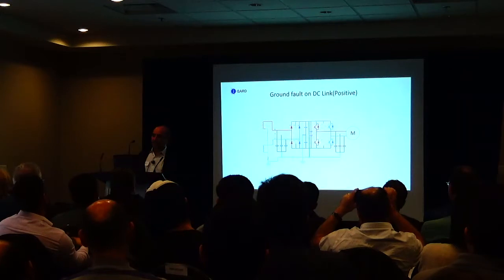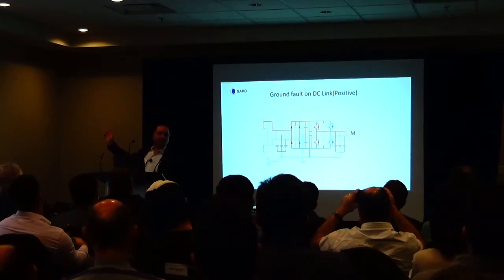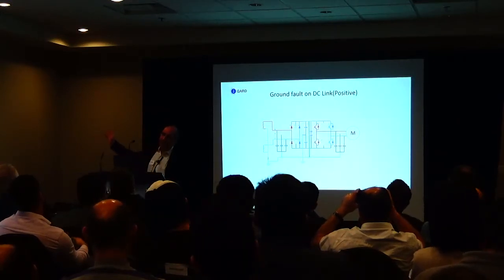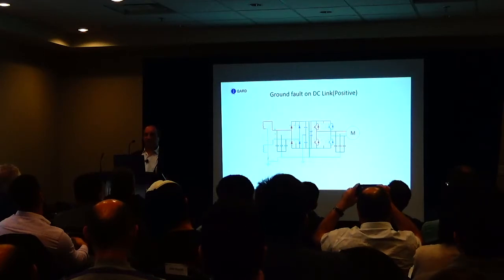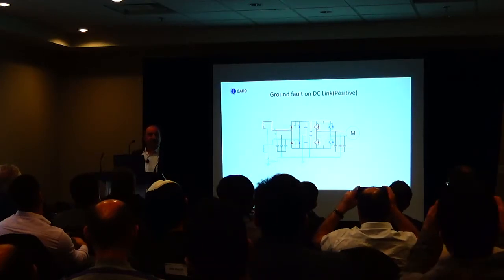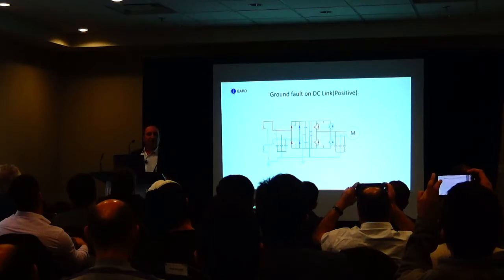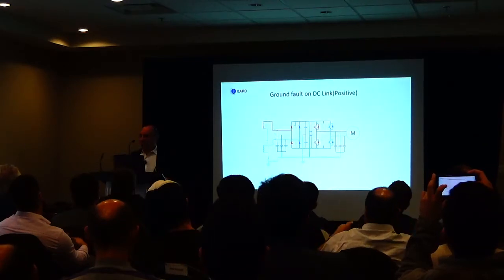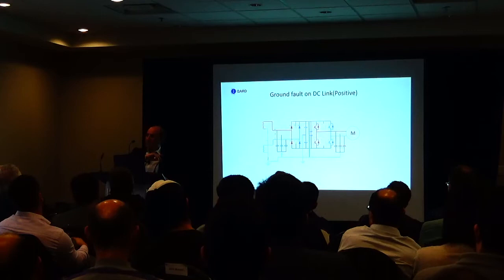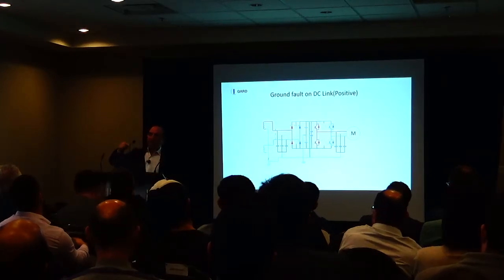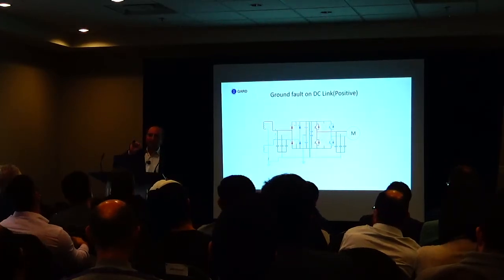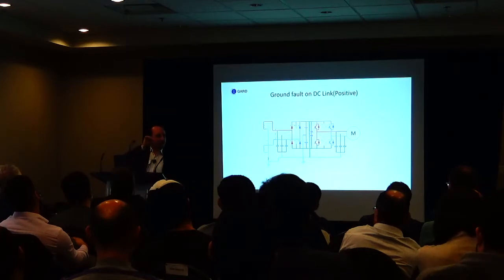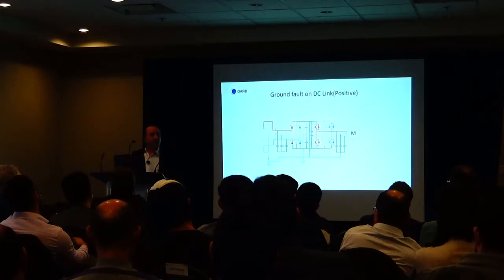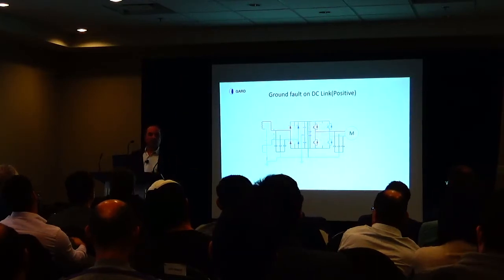We had an old DSP system on a hospital near here, Brampton Hospital, brand new hospital, they put in an old DSP system. They had a fault on the output of a variable frequency drive. And what we noticed was that all three lights are on. The DSP system is such a device that it tells you what phase the fault is on when you have a fault. But all three of them were on. Well, you can't have a fault on all three phases. But they were time sharing the fault.